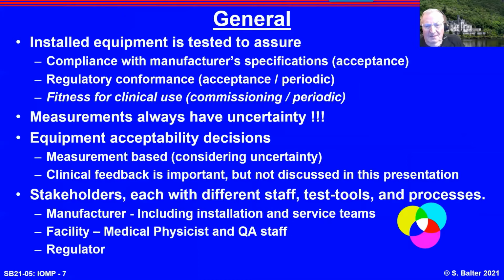So we're testing compliance with manufacturer specifications. This is basically an acceptance, and I'll show you in a few minutes what the manufacturers do to deliver acceptable equipment. Regulatory conformance at acceptance, periodically per your local regulators. Fitness for clinical use: this is commissioning of the equipment, a term that's actually better known to the therapy community than the imaging community, and periodic. Here, your knowledge as professional medical physicists as to the clinical use of the equipment and the consequences of a poor decision should come into play.